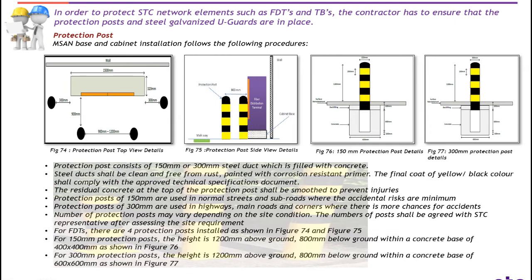In order to protect STC network elements such as FDTs, the contractor has to ensure that protection posts and steel galvanized U-guards are in place. MSAN base and cabinet installation follows the following procedure. Protection posts consist of 150 mm or 300 mm steel duct filled with concrete. Number two: steel duct shall be clean and free from rust, painted with corrosion-resistant primer; the final coat of yellow-black color shall comply with the approved technical specification documents. Number three: the residual concrete at the top of the protection post shall be smoothed to prevent injuries.